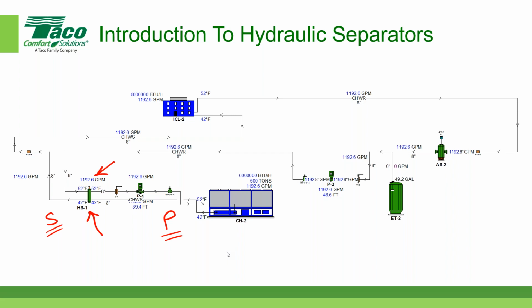Actually, you don't actually have to monitor the flow across the bridge, as long as when you set up the balancing between the primary and the secondary circuit. Remember that they are hydraulically separated in the sense that the flow in the primary circuit does not influence the flow in the secondary circuit. And the opposite is also true. The flow on the secondary circuit does not influence the flow in the primary circuit. So if both circuits are properly balanced, then you actually don't need to have flow meters, because once they're balanced, then as you change the load on the secondary side, you would be modulating the flow, usually as a function of a variable speed drive in the secondary side.